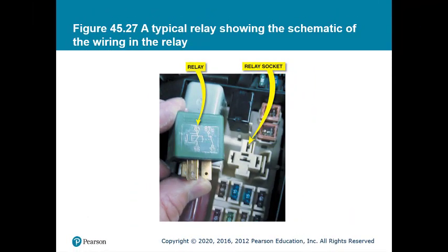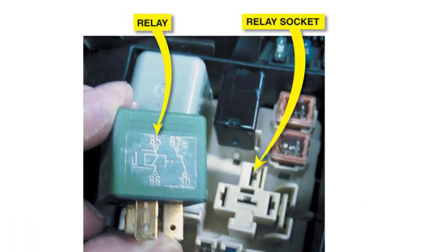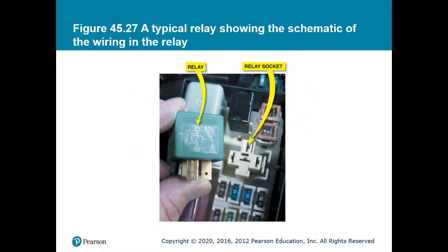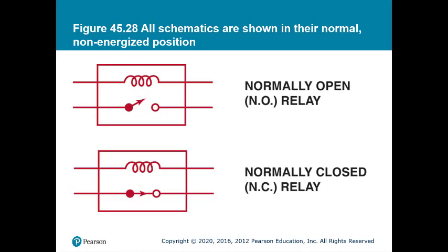Figure 45.27 shows a typical relay, and it also shows the relay socket. If you notice on the side of the relay, it actually gives you a little schematic. Many relays have that schematic on them. Many relays also don't have that schematic, but this is kind of nice because it shows you what the pins mean. Figure 45.28 re-explains what we talked about already, that all schematics are shown in their normal non-energized position. I say off, but non-energized position.